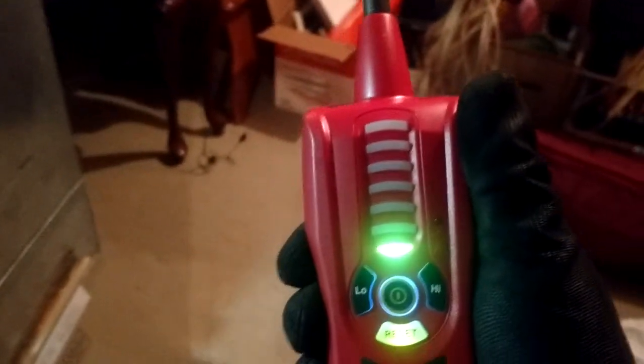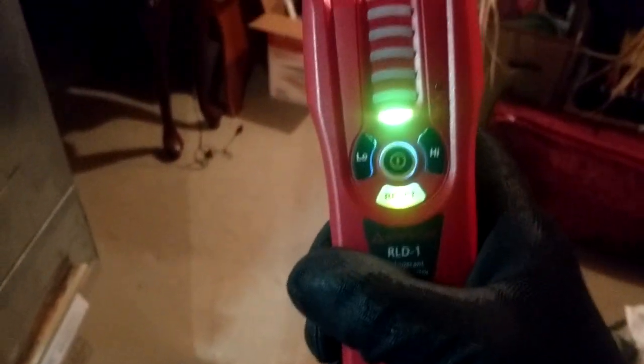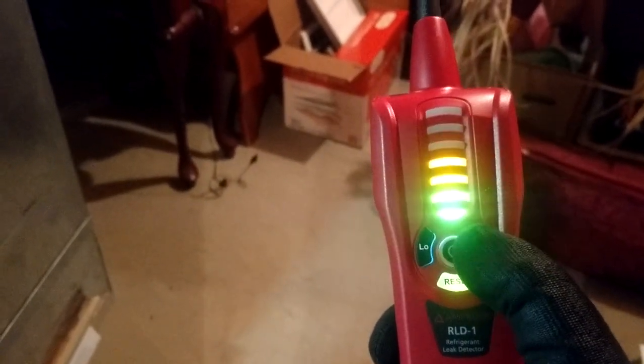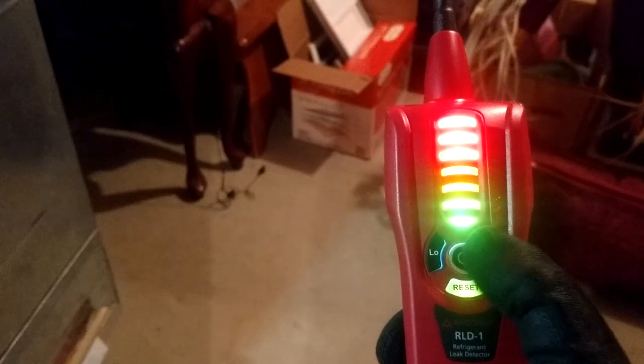This is the Amprobe RLD-1 — it's a pretty good leak detector, I really like it. I've found a lot of leaks with it. It's good on R-22 and 410A both. The thing is quiet while it's running, no beeping to annoy you — it only beeps when it finds a leak. You've got auto and manual sensitivity, and a low, medium, and high setting: low is the green lights, medium is up to yellow, and high is the red.